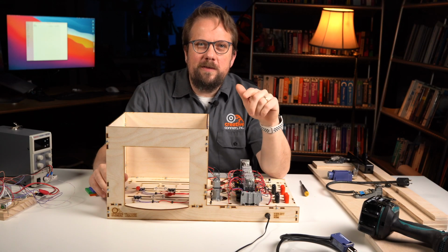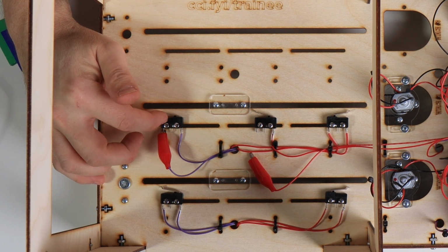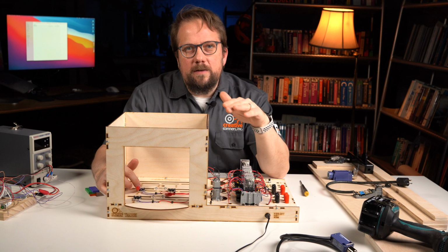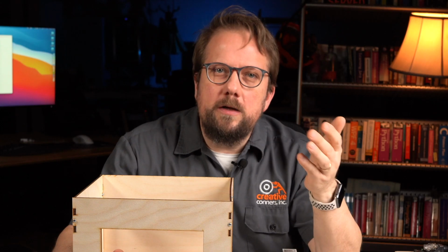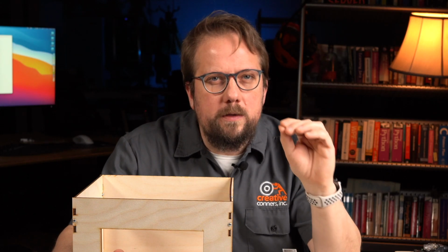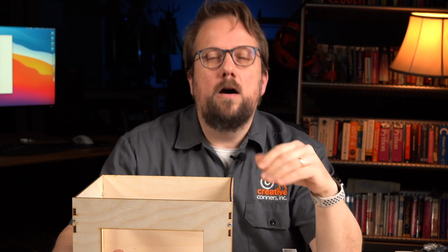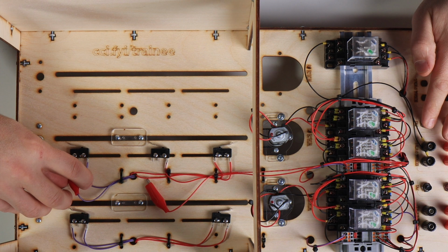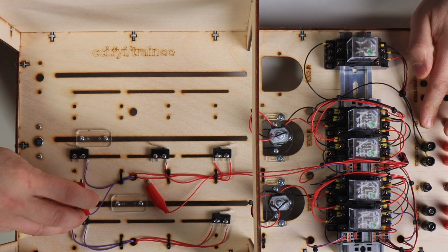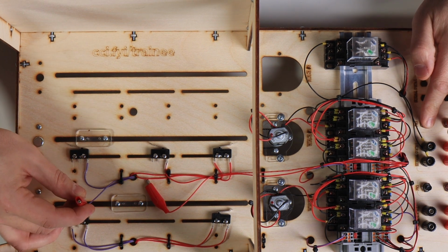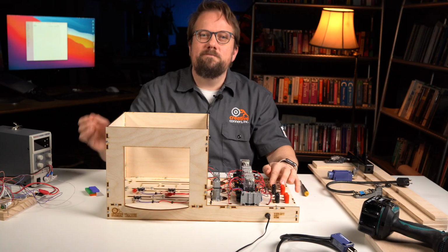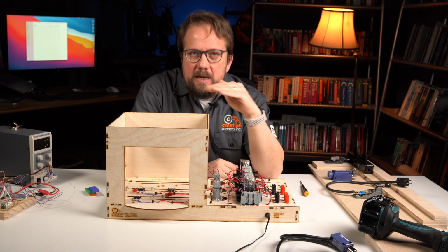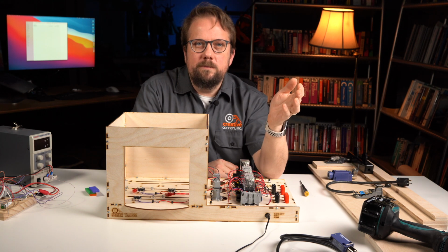Okay, let's try this again with the limit switch at the end of the track that's wired normally closed. This is the stock configuration for a trainee. Here the logic is basically, tell me all the time that you're okay, otherwise I'm going to stop. So if I start moving towards the limit switch, as soon as I disconnect that wire, the motor stops. That's much better. Now, if there's a failure, the motor immediately stops and it won't crash.